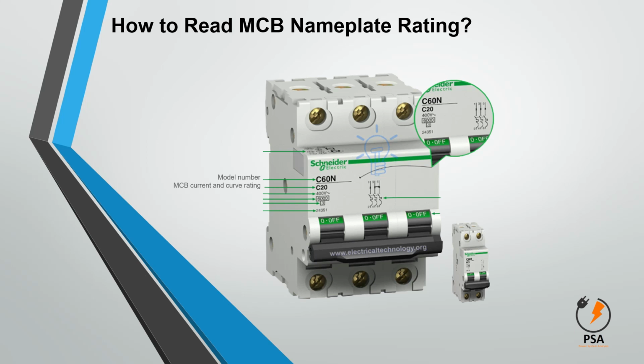As shown in the example, it is mentioned C20. The first letter shows the characteristic curve. There are 3 characteristic curves in common use. The B curve indicates that the short circuit rating of the device is in the range of 3 to 5 times the standard rated current, which means the time for trip initiation is short, i.e., it will be fast acting, like for protecting sensitive electronic devices and equipment. The C curve indicates 5 to 10 times and the D curve indicates 10 to 20 times. Be very careful while selecting this.